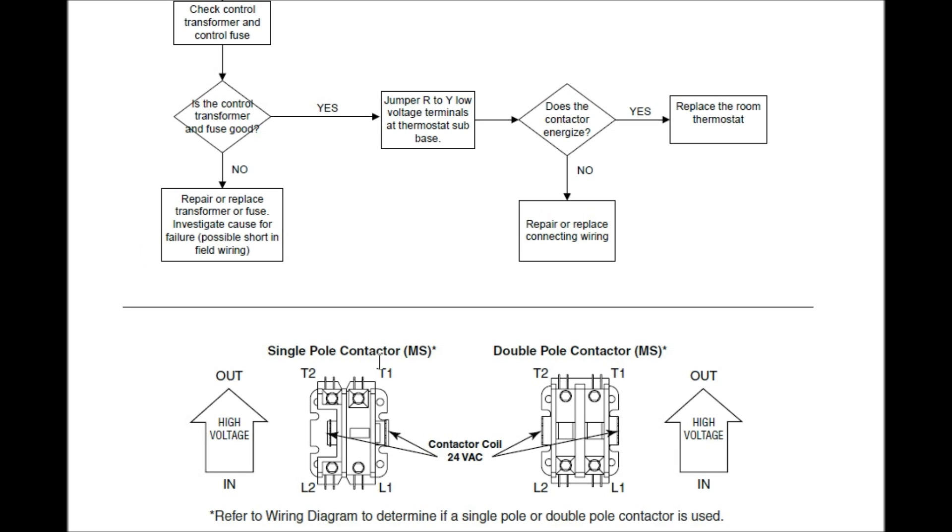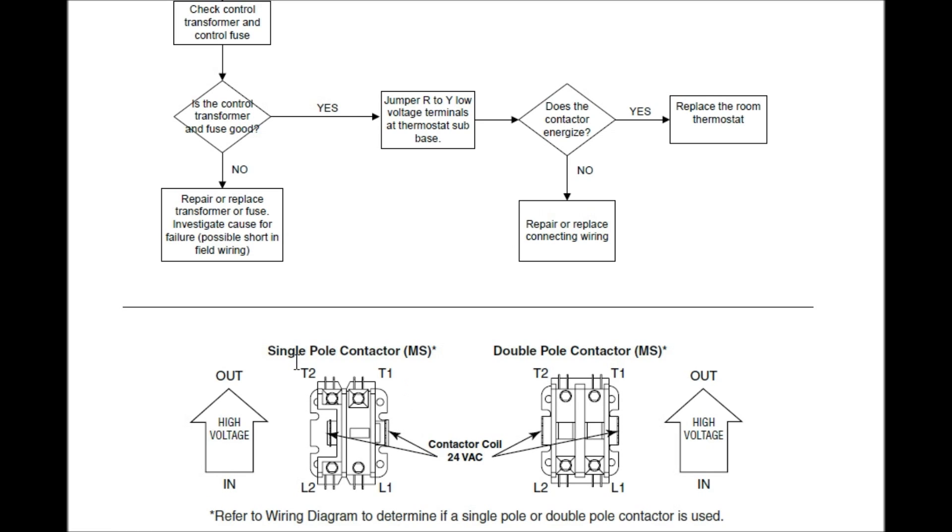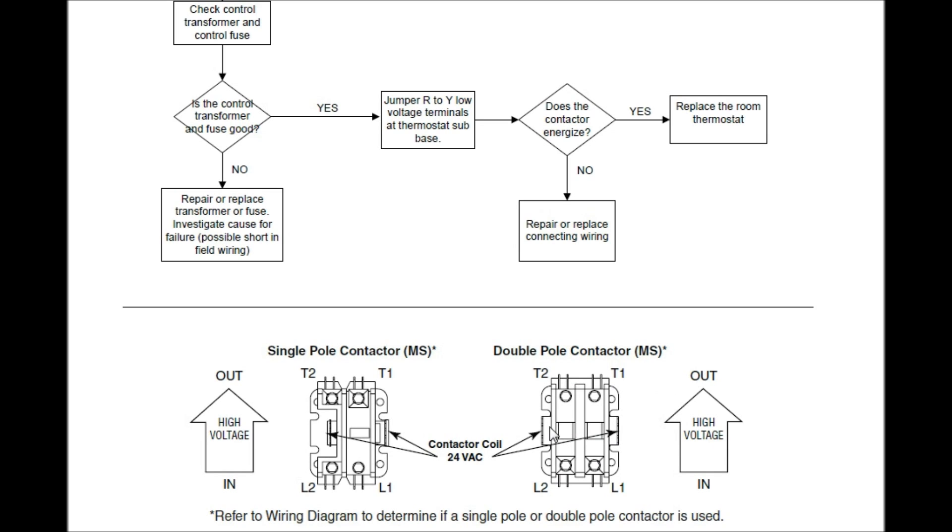What we have here is a single pole contactor and a double pole contactor. Right here, we have L1 and L2. That is our line in, that's our voltage coming in. T1 and T2, and T1 and T2 over here, and L1 and L2 over here, it's the same. That's our line voltage coming in, and this is our line voltage going out. Here's the contactor coils. They're actually asking us to test to see if we got 24 volts.